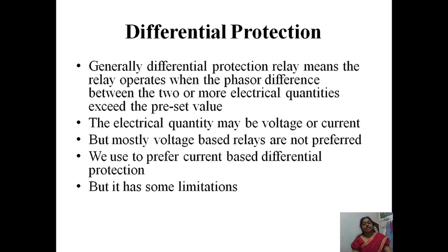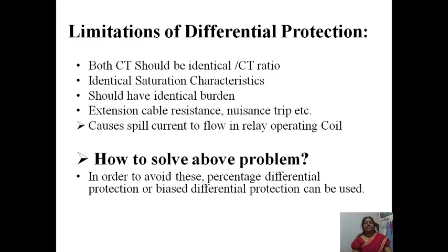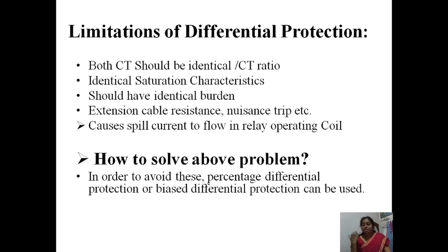Protection based on the circulating current principle — that is, current-based differential protection — has certain limitations. In differential protection, we require two identical CTs: their CT ratios must be matched, their saturation characteristics must be equal, and they must have equal burden. But in practice, this is not possible. No two CTs are identical. Because of this, it causes spill current to flow in the relay operating coil. Also, external cable resistance causes relay maltrip or nuisance trip.